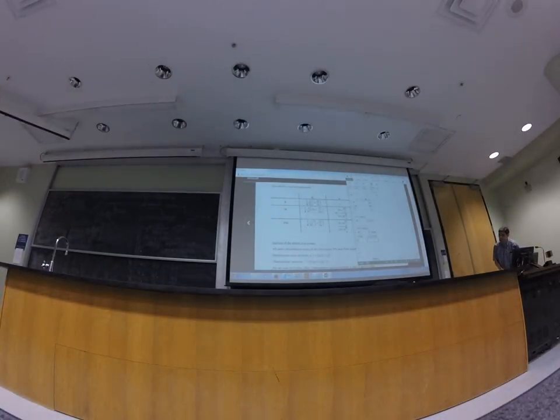Small delay is bad, and I think I may have made the step change a bit earlier, and I may have underestimated a bit the delay. So this tuning is not going to be the greatest, but let's say it's in action. Anyway, that's what we got. Let's see. Might get a good score, but it will be a bit too aggressive. But it also gives a good opportunity to talk about what you look for.